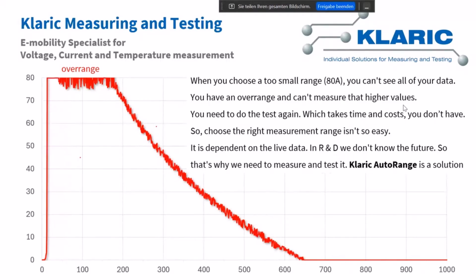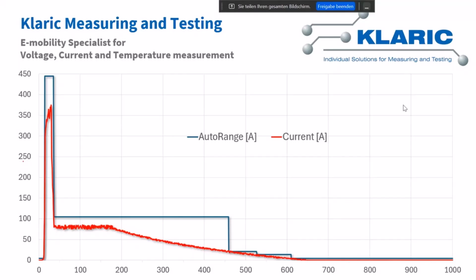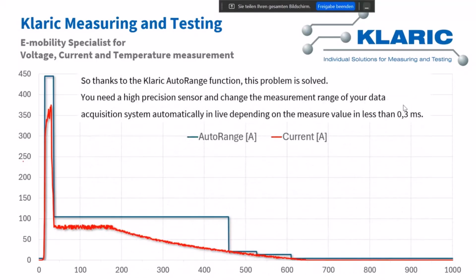Thanks to the Klaric auto range function, this will change the measurement ranges automatically. You can see here, when the current is high, automatic Klaric will choose the highest measurement range. And when the signal becomes lower, automatic Klaric will change the data acquisition system to a smaller range. Even when we come to the quiescent sleeping current measurement, automatically we will choose a very small range, and then, of course, we can see this signal very precisely. And when I say we change the ranges, usually we do this in less than 0.3 milliseconds. So this is quite fast, depending on the ranges.